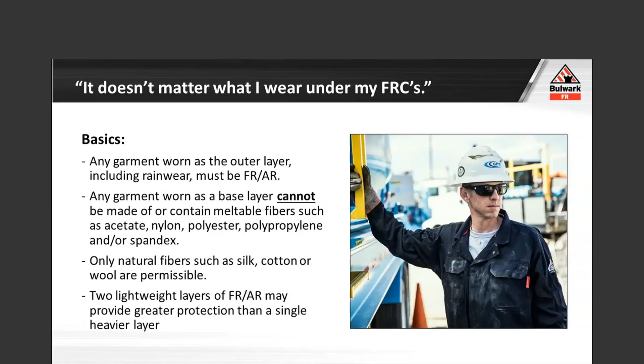So one of the ways that we can eliminate that is introducing flame-resistant arc-rated base layers, because what they do is protect against, especially in our electric arc world, that outer layer failing. For example, if I have a piece of equipment that I have been told a reasonable estimate, if it is an arcing fault, will be 5 calories of incident energy. If I'm wearing an 8-calorie shirt, I'm confident that I've got more than enough protection and insulation for that 5-calorie exposure. Now, that 5-calorie exposure is typically at 18 inches, and that typically is going to be, say, 2 to 4 cycles of closing time, depending on the equipment.